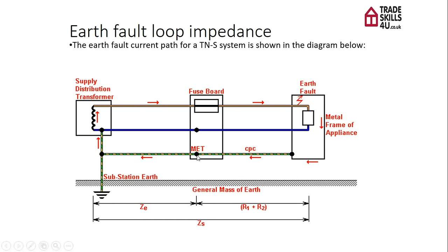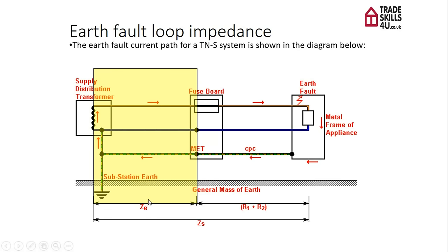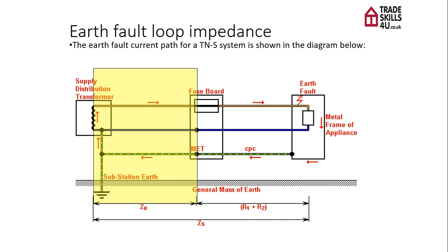In order to do that, we have to disconnect it to test it because we don't want to be testing any other conductors. We might be getting parallel paths if we don't disconnect it. The area that we're going to measure is this external section here, where we're measuring the incoming earthing conductor along with the incoming line conductor. And that is going to give us a value which is going to go on our certificate as ZE. This test has to be done at the origin of the installation with the main earthing conductor removed and the installation safely isolated.